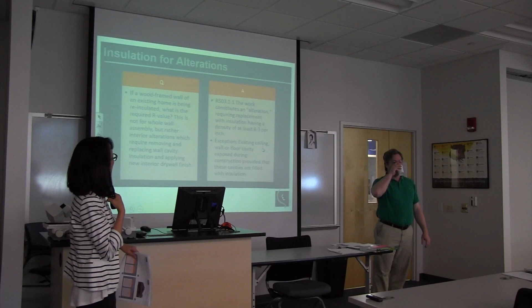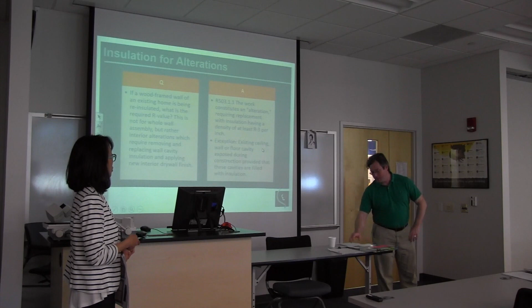On insulation for alteration: if a wood-framed wall of an existing home is being re-insulated, what is the required R-value? This is not a whole wall assembly, just an interior alteration. The answer, based on R503.1.1, is that the work is an alteration requiring at least R3 per inch. If it's just an existing ceiling, wall, or floor cavity exposed during construction, those cavities are just filled with insulation — you don't need to meet full code. So that's just a reasonable approach.